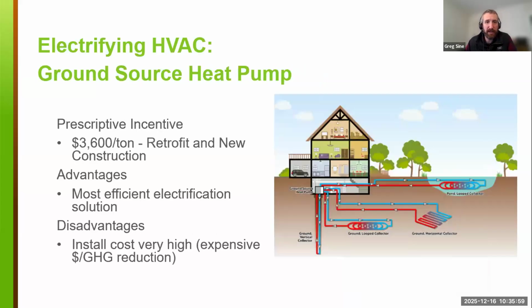Next slide, please. And then the last overarching technology type would be ground source heat pumps. These have the highest prescriptive incentives available, but they're also one of the more costly to install, given the relative complexity of the system and the need to install some type of ground heat exchanger, whether it's wells or buried loop. You can see several options in this graphic here. One nice thing about geothermal is the efficiencies or COP of the system generally tends to be higher because of the relative stability of ground temps as opposed to air temps.